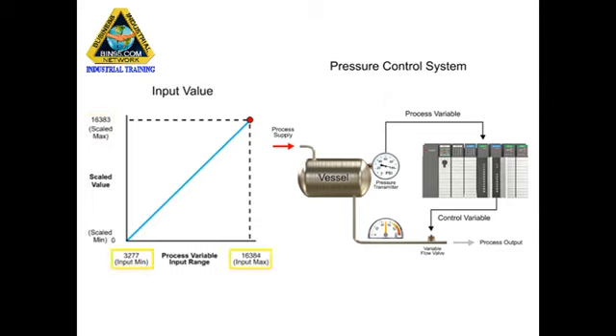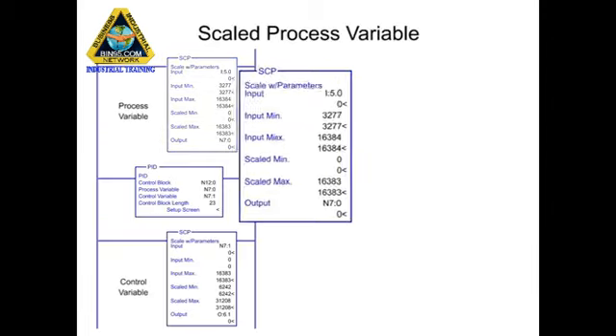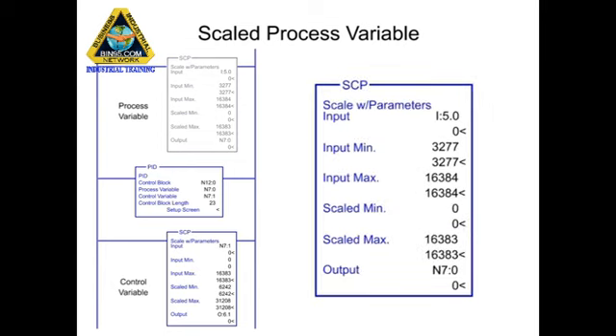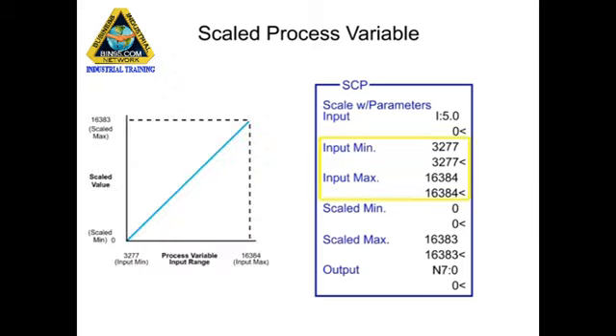The input value is scaled to a range of 0 to 16383 compatible with the PID instruction using the Scale with Parameters instruction, or SCP. The input parameter of the SCP instruction contains the memory address of the analog input module. The input minimum and input maximum are programmed as the smallest and largest values produced by the analog input module.